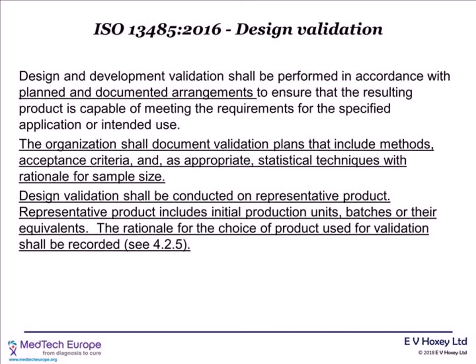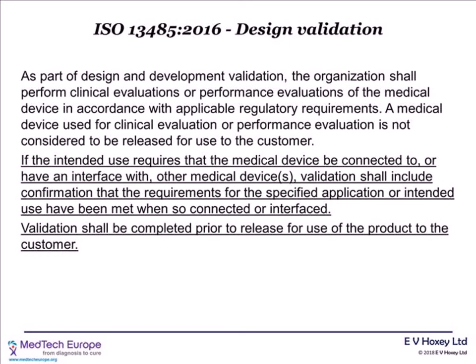Design validation now has a greater emphasis on the plan for validation, which needs to be explicitly documented, and that plan needs to include the validation methods, the acceptance criteria, and what statistical techniques are going to be applied, and needs to be carried out on demonstrably representative product. Indication of what that representative product might be. It also goes on as well, continuing to need clinical evaluation or performance evaluation in accordance with applicable regulatory requirements, an explicit mention of interface and validating that the device works as intended when connected to or used with medical devices when that's the intention, and the validation being completed prior to release of product to the customer.